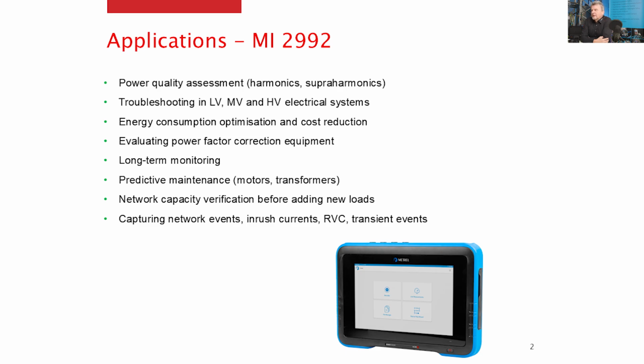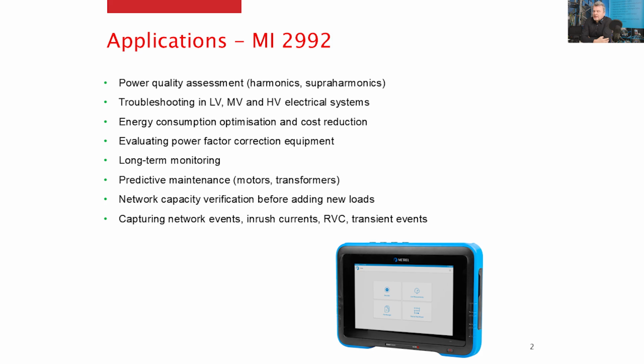Based on the memory, which is integrated in the instrument itself, and possibilities to insert external SD card up to 32 gigabytes, it could be used for long-term monitoring, more than 1 year, for example. With the simultaneous detecting of different anomalies, also measuring of temperature, it could be used as predictive maintenance for measuring motors and transformers. And also for verification of the network capability before adding new loads. Simultaneously with the recording, the device could capture events like inrush currents, voltage dip, swell, interruptions, RVCs, and transient events.